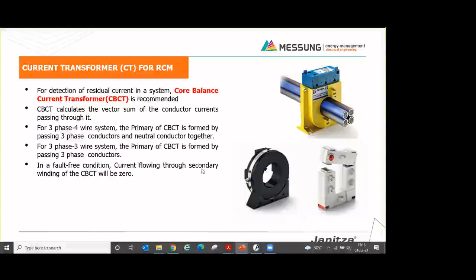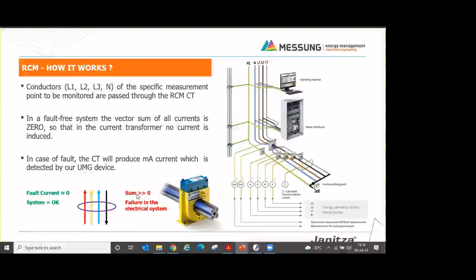Now we'll see how it works. So as I said, we pass all the phase and neutral conductors together through a CT, and if the resultant current is zero or nearly equal to zero, then the system is fault free. And in case there is a fault, then the resultant or vectorial sum would not be equal to zero.